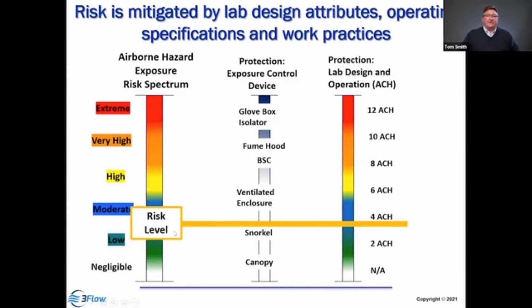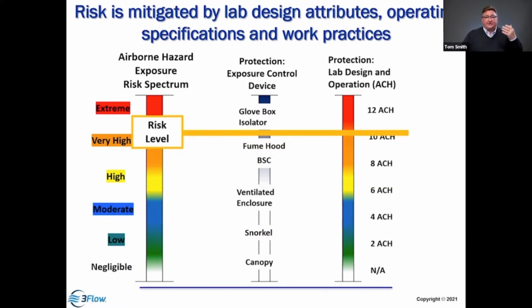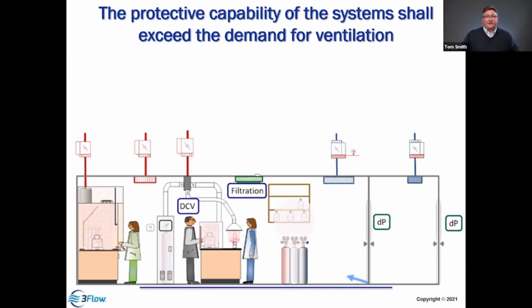As that risk level increases, so do the requirements for the hoods. You can start with a canopy providing low to no containment and low to no protection, a snorkel a little bit more, followed by a ventilated enclosure or a fume hood. If a fume hood's not good enough, maybe you need to go to a glove box or some kind of special isolator. And the same thing can be said for the laboratory. As we increase the level of ventilation and ventilation effectiveness, we can begin matching the exposure level. So knowing the risk and knowing the protective capability, we can match these to make sure that they're safe. And we're going to test the fume hood to make sure that it provides an adequate level of protection.